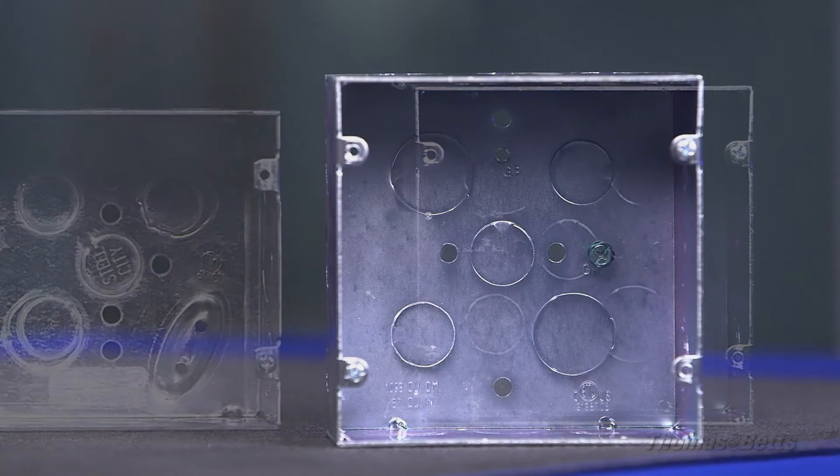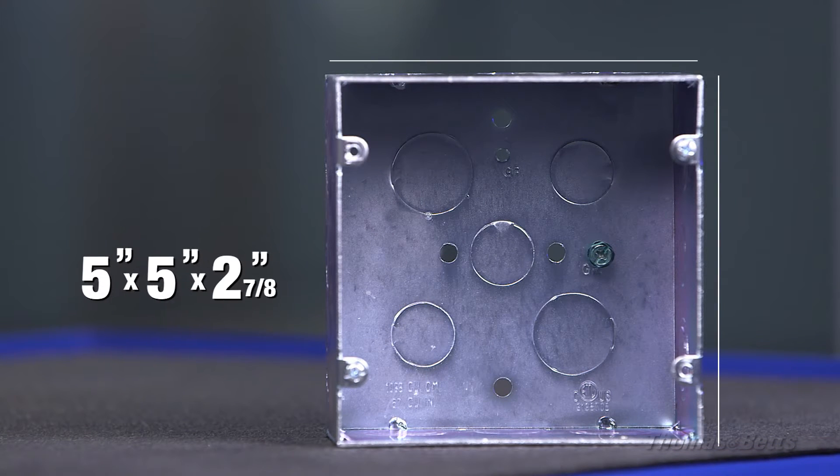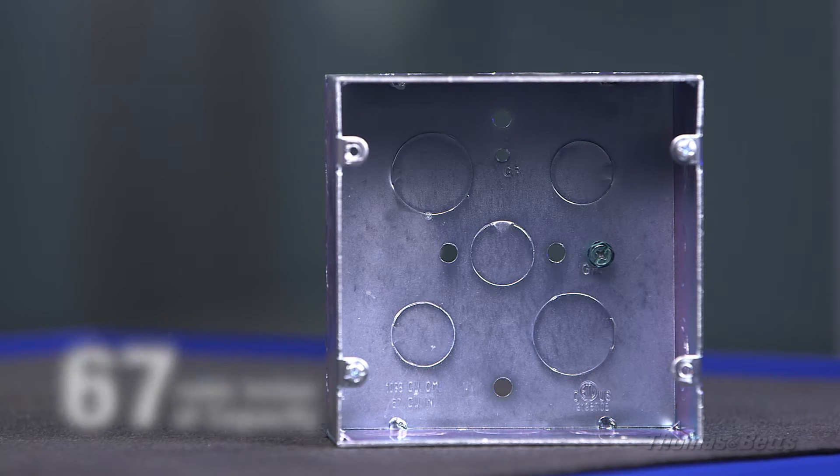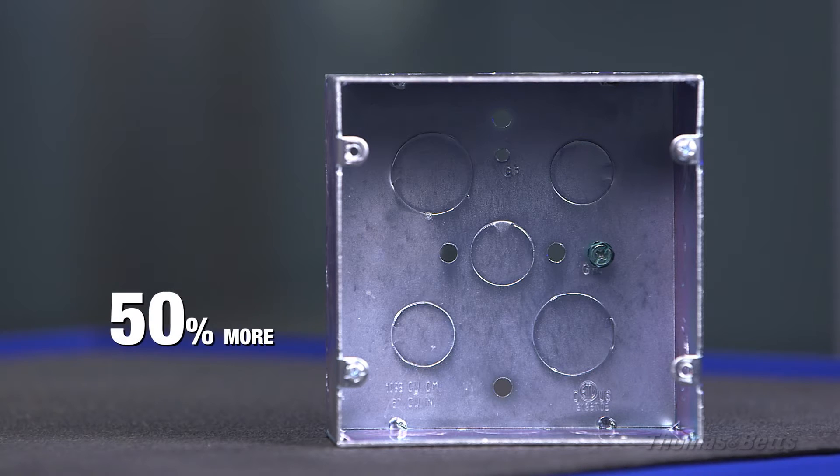Overall box dimensions are five inch by five inch by two and seven eighths inch for up to 67 cubic inches of capacity. That's more than double the capacity of a four square deep box and fifty percent more capacity than a four and eleven sixteenths inch deep box.